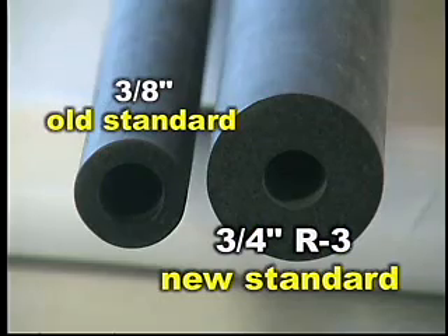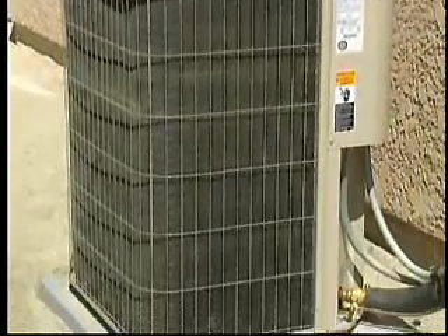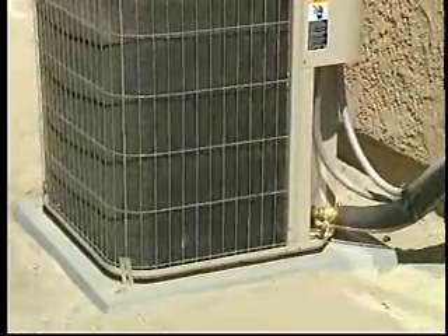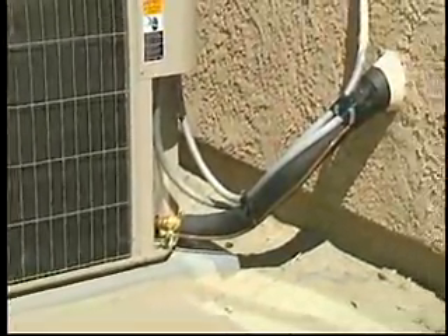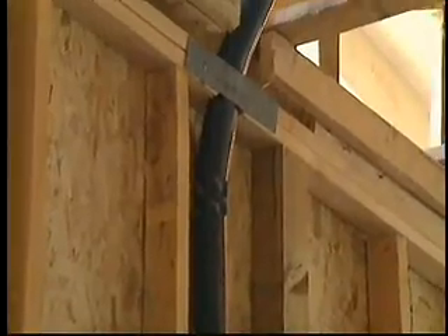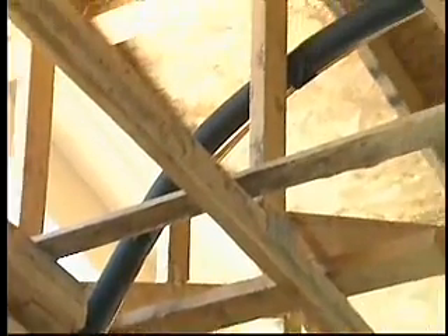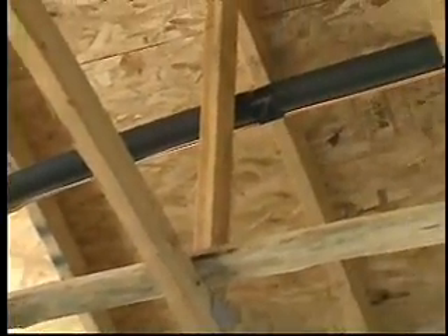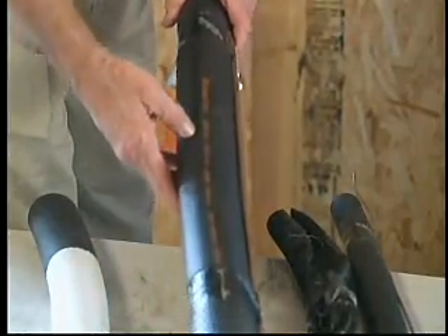And John, how do you determine the right amount of insulation for an air conditioner line set? Well, the code, residential Title 24, requires R3. So you first need to know the R value you're trying to get. The second component is you need to find out what the K factor is of the insulation itself. That's another way of saying thermal conductivity. And you simply have the R value times the thermal conductivity, or the K factor, and that equates to the thickness.